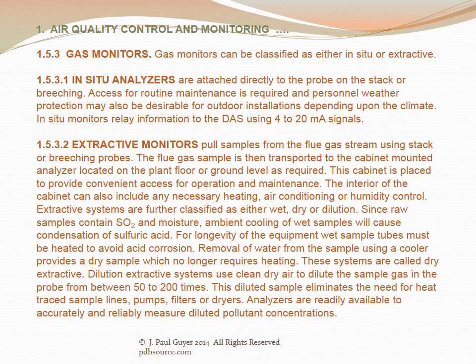Gas monitors can be classified as either in situ or extractive. In situ analyzers are attached directly to the probe on the stack or breaching. Access for routine maintenance is required, and personnel weather protection may also be desirable for outdoor installations depending upon the climate. In situ monitors relay information to the DAS using 4 to 20 milliamp signals.